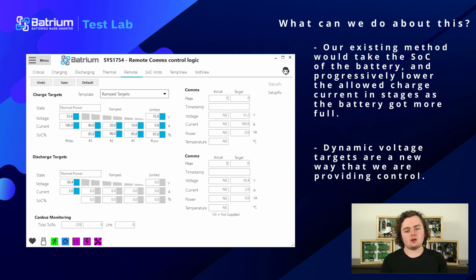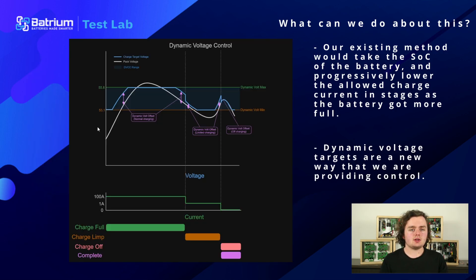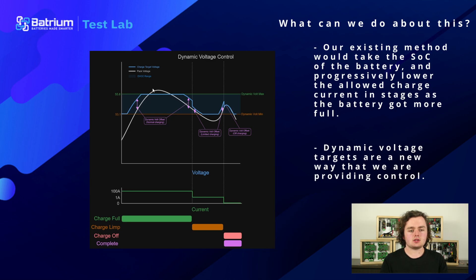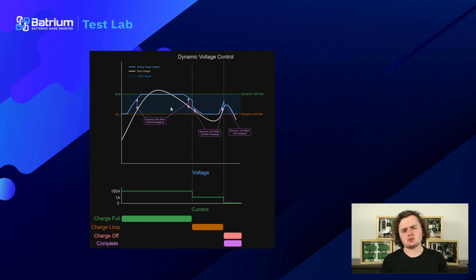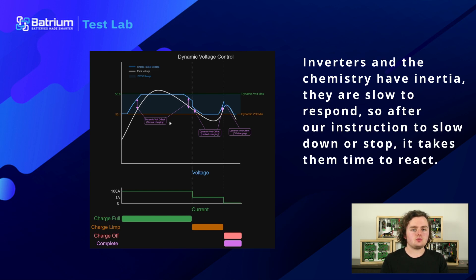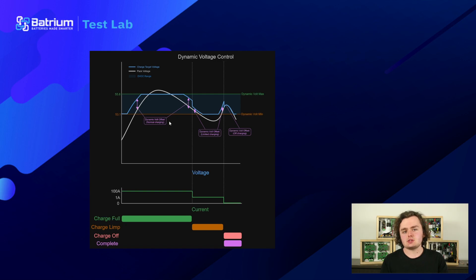Dynamic voltage targets are a new way to do it, and here's a diagram showing how it works. This routine is bound by two values — the dynamic volt min and dynamic volt max, which you can see in the software there. When the curve isn't anywhere near the target voltage it's clamped at the low value, and if it exceeds the maximum charge target it's clamped at the higher value. Inverters and the chemistry have inertia — they're slow to respond — so after instructions to slow down or stop it takes some time to react. This means cells can surge up in value at the top or bottom of charge, but it's only if it stays there that it warrants concern.